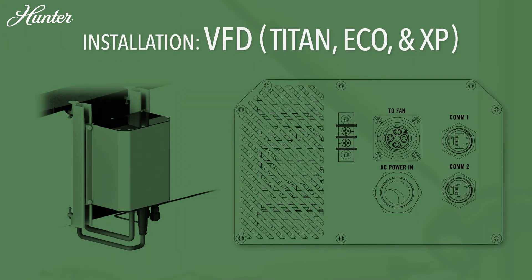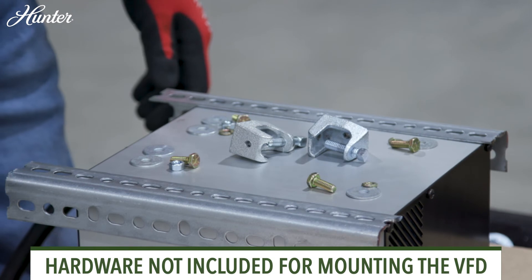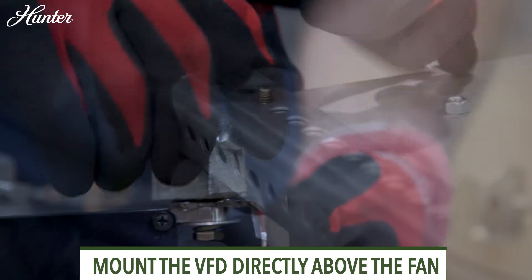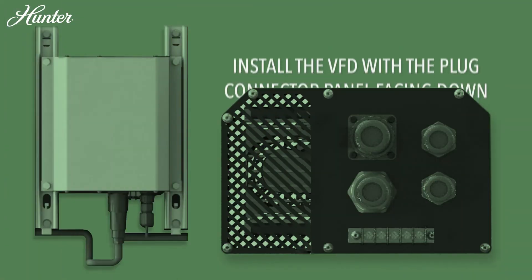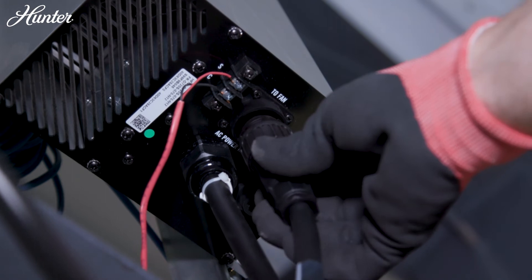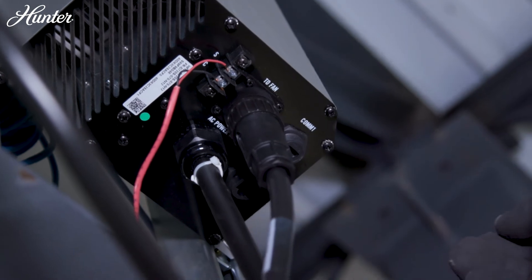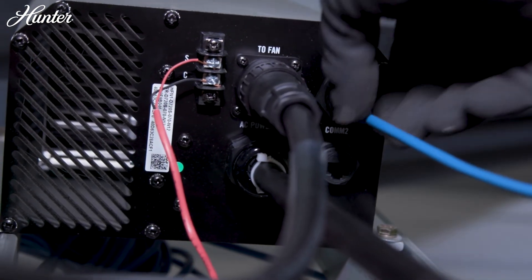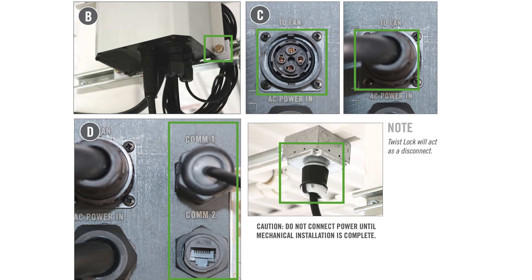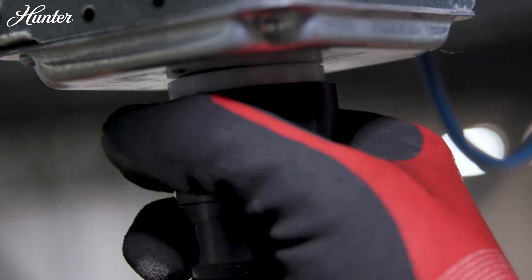VFD: Prep the variable frequency drive for mounting to the structure. VFD hardware is not included and mounting methods may vary. Mount the VFD directly above the fan, with the plug connector panel facing down. Connect the motor cable from the fan to the VFD, carefully aligning the pins within the connector before performing a clockwise twist to lock in place. Connect the Ethernet communication cable to port COMM1, and run the other side of the communication cable to the HMI. Plug the VFD power whip to the appropriate power receptacle and twist clockwise to lock.